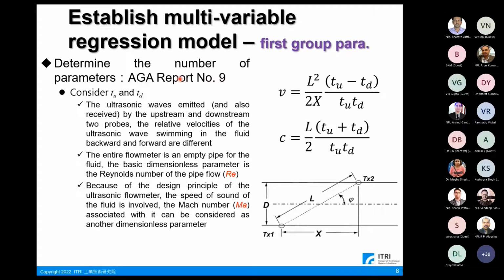According to the AGA report number 9, the ultrasonic waves are emitted and received by the upstream and downstream probes. The relative velocities of the ultrasonic wave traveling in the fluid backward and forward are different. The entire flow meter is an empty pipe for the fluid. The basic dimensionless parameter is the Reynolds number of the pipe flow. Because of the design principle of the ultrasonic flow meter, the speed of sound of the fluid is involved. The Mach number associated with it can be considered as another dimensionless parameter.